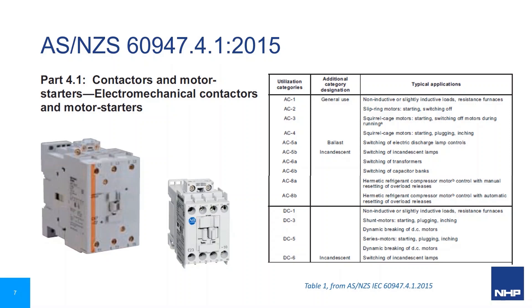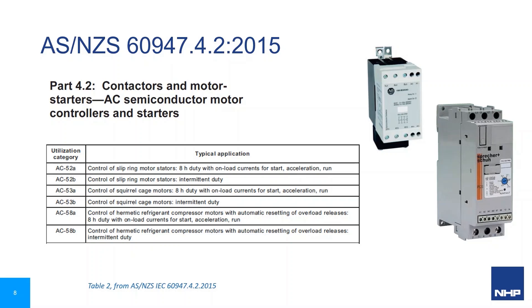The individual product standard for electromechanical contactors is IEC 60947 part 4.1, and defines their utilisation categories for switching capabilities for many different load types for their main poles. The auxiliary contacts of a contactor have ratings based on utilisation categories for electromechanical control circuit devices. For motor starters and controllers with semiconductor switching, product standard IEC 60947 part 4.2 defines the utilisation categories for electronic soft starters and solid state contactors. Intermittent duty is used for soft starters where they have an internal or external bypass contactor.